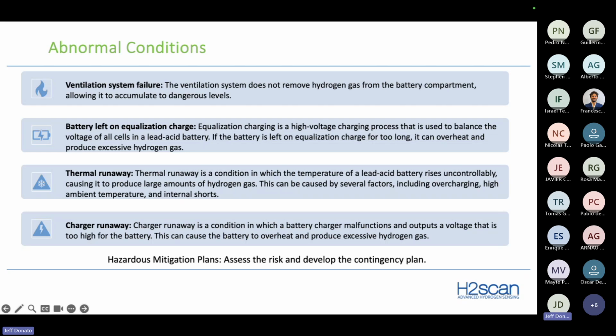The one condition I was talking about where I personally went to a site that had a valve regulated battery and thermal runaway. It was at a defense contractor, and they had a room full of GNB or Exide Absolite batteries, and they were the 20-year design life valve regulated lead acid batteries. It was in a very small room, and the room was filled with about 4 strings of large batteries. So the room was a good size, but it was small for the amount of batteries they had in the room.